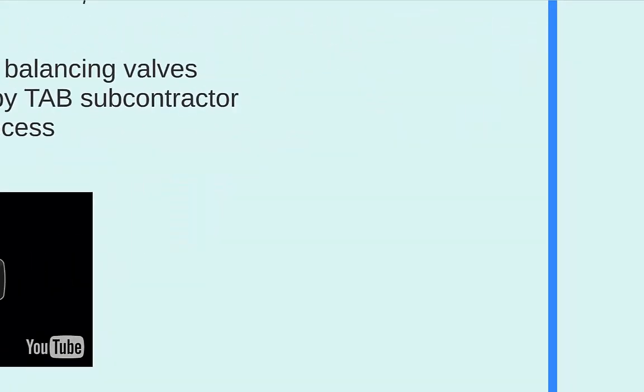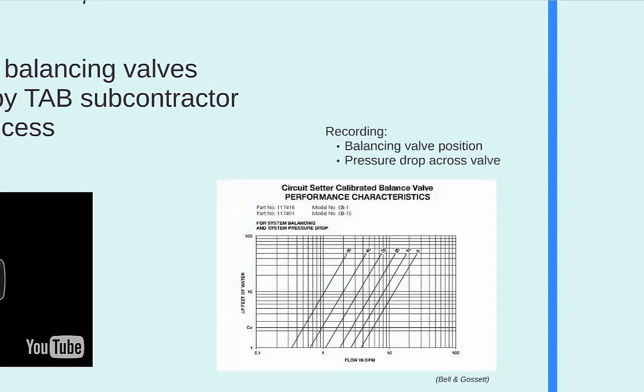As I said, what he's trying to do here is to determine the flow rate entering a chilled water coil in a rooftop unit. He is doing this by looking at the position of the balancing valve, as well as taking the pressure drop across that valve. Those two values can be used in conjunction with the balancing valve manufacturer's performance data table to determine the flow rate of water flowing through it.